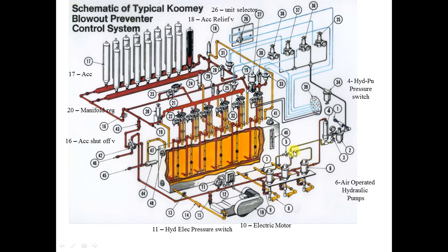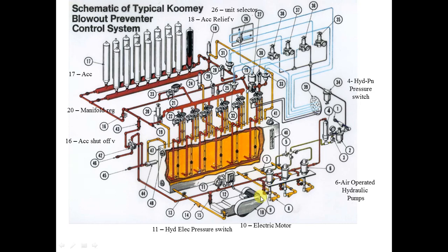Each pump — whether electric or air — must also have a check valve. Number nine is the check valve. Without it, when pumping stops, pressure would be released back to the reservoir. The check valve is a one-way valve: it allows pressure to build but prevents it from releasing back through the pump.